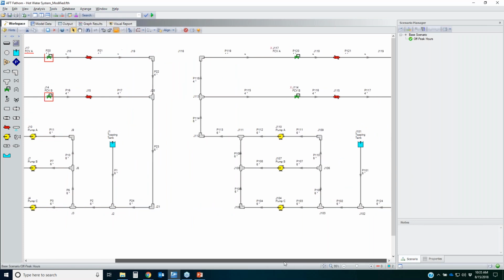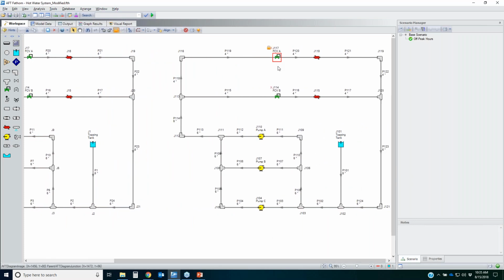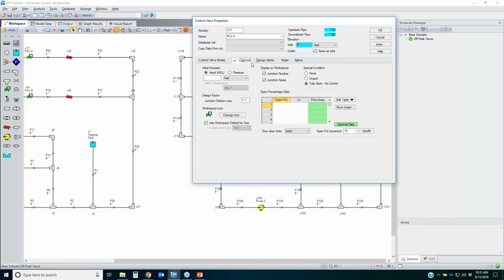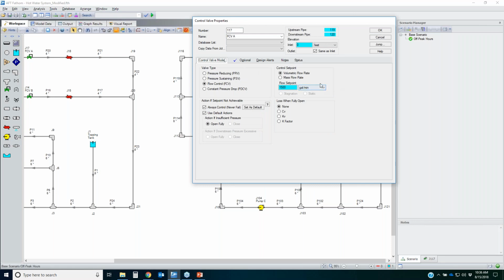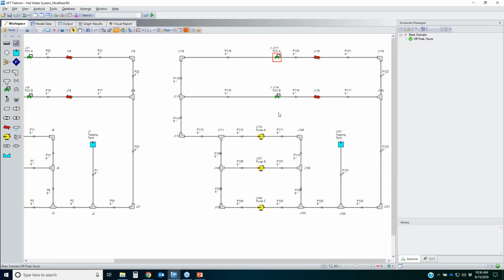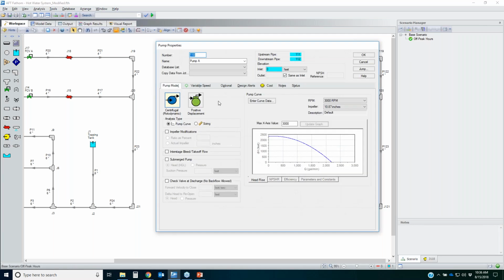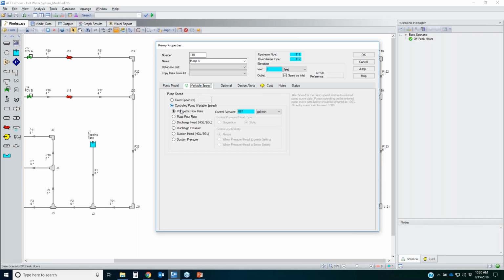System on the right-hand side, I went into the control valve junctions. On the optional tab, I said fully open, no control. Fully open, no control, I'm going to have no loss. And the reason for that is because if I have my pumps operating on a variable speed drive, I don't need the control valves. So I'm ignoring them. On my pumps, for each of these, what I did was I went to the variable speed tab and I specified a flow set point, 667 gallons per minute. That's 2,000 divided by 3 pumps right there.